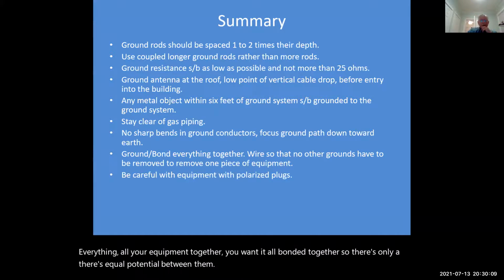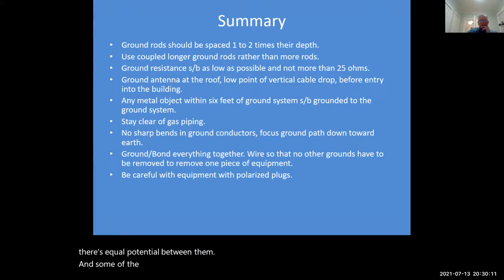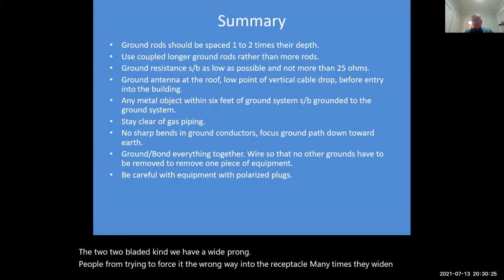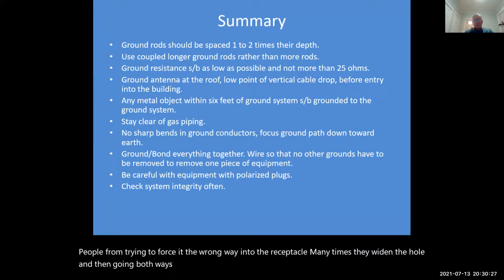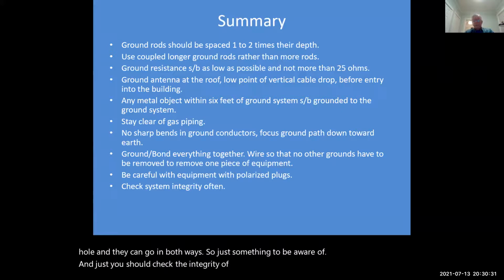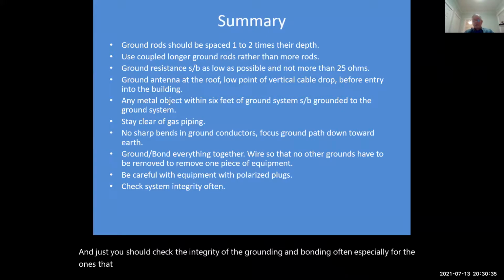And some of the polarized plugs, especially the two-bladed kind where you have a wide prong, people trying to force it the wrong way into the receptacle many times widen the hole and they can go in both ways. So just something to be aware of. And you should check the integrity of your grounding and bonding often, especially for the ones that are buried in the ground.